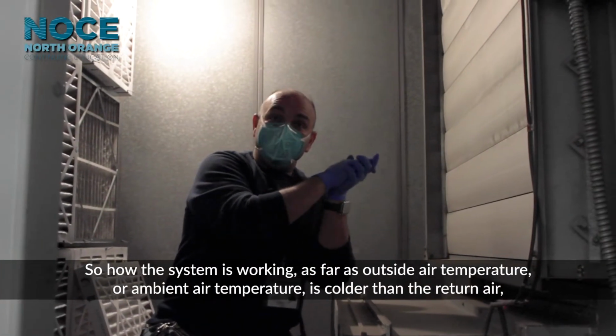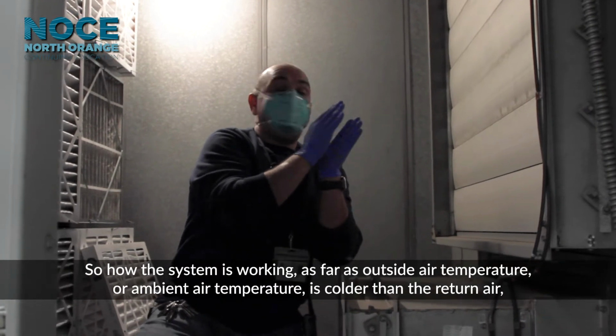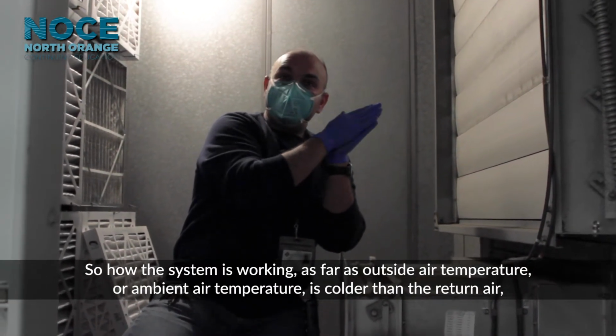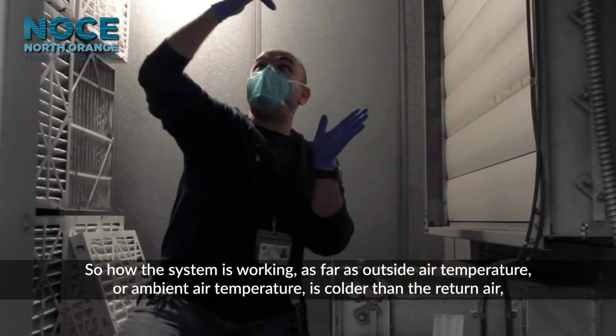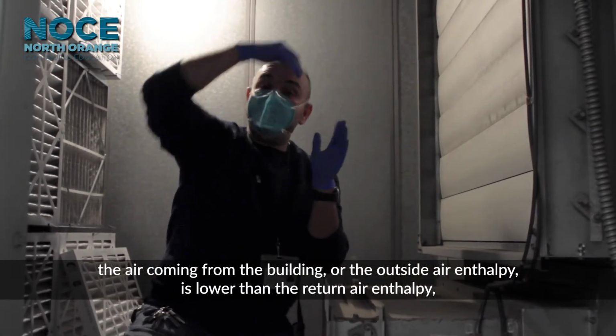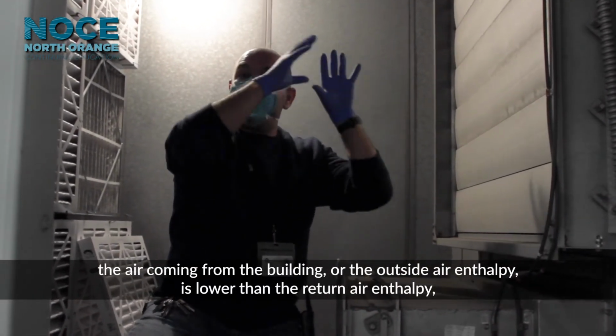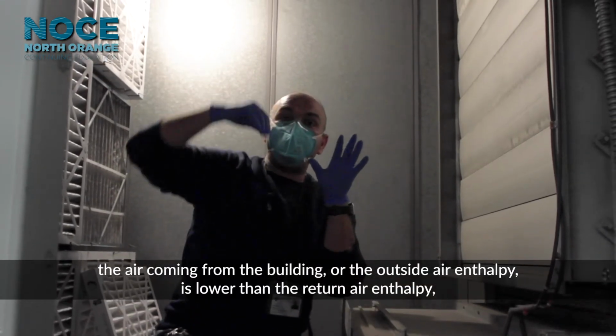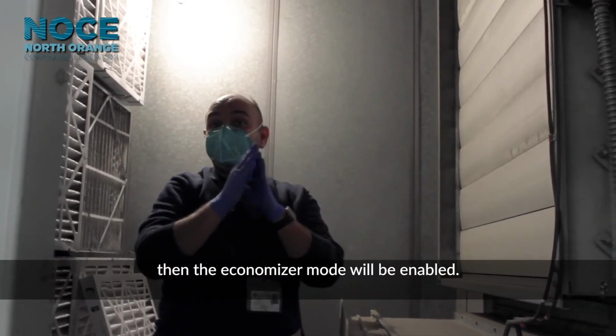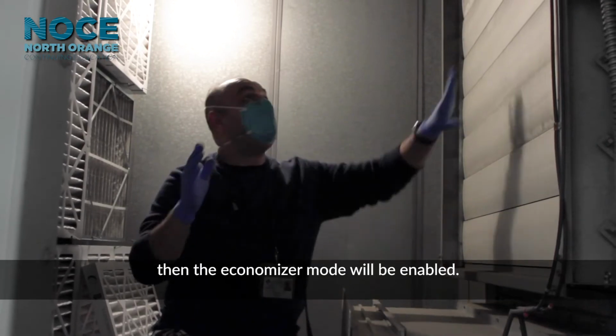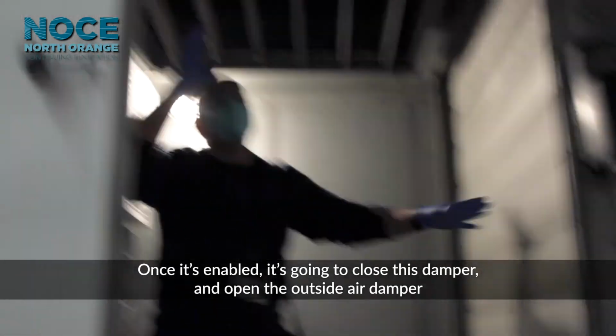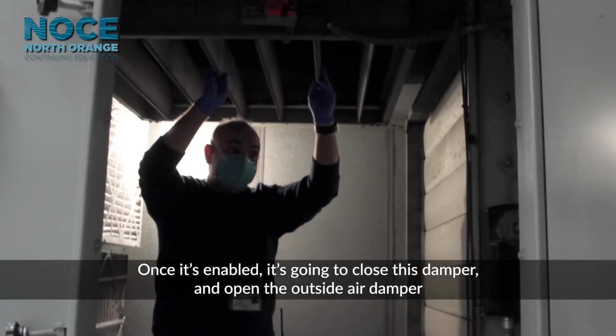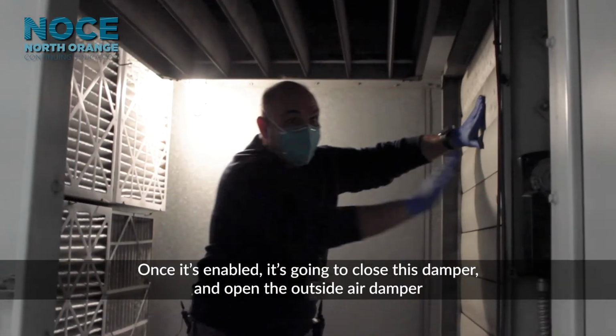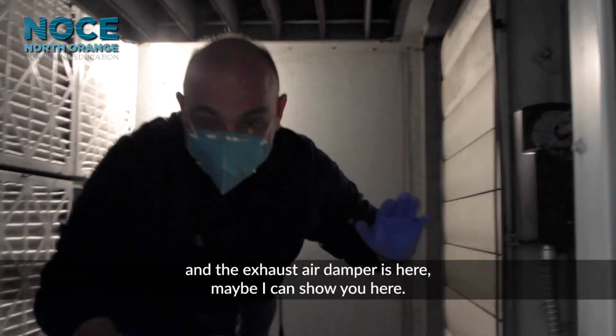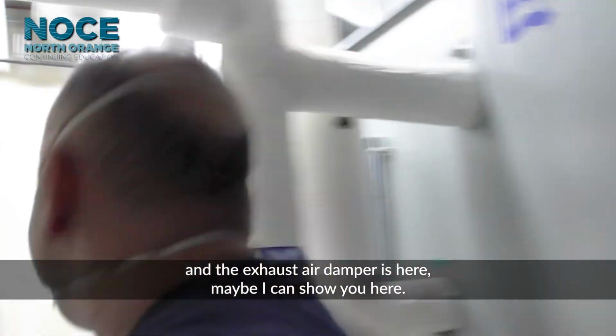So how the system is working: as far as the outside air temperature, if the ambient temperature is colder than the return air, the one coming from the building, or the outside air enthalpy is lower than the return air enthalpy, then the economizer mode will be enabled. So once it's enabled, it's going to close this damper and open the outside air damper, and the exhaust air damper, it's here. Maybe I can show it here.